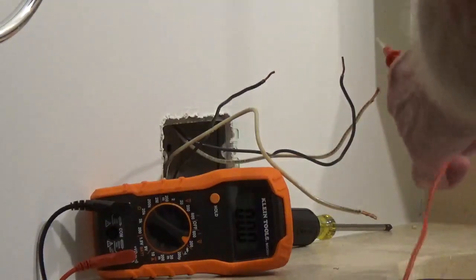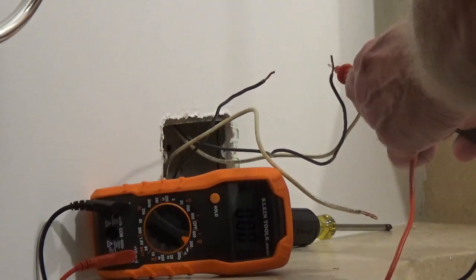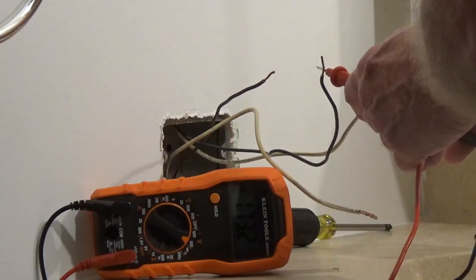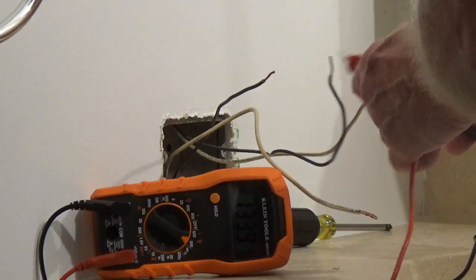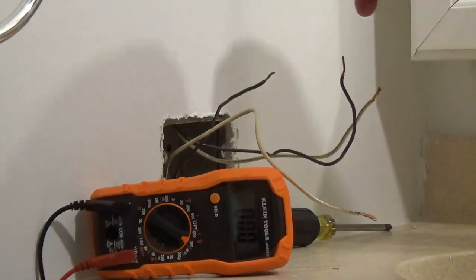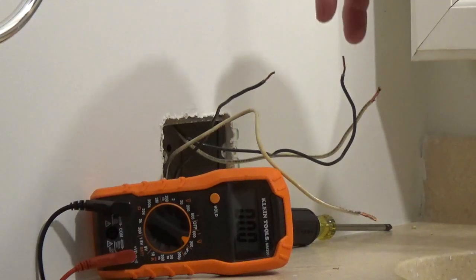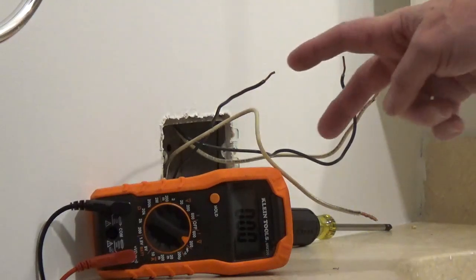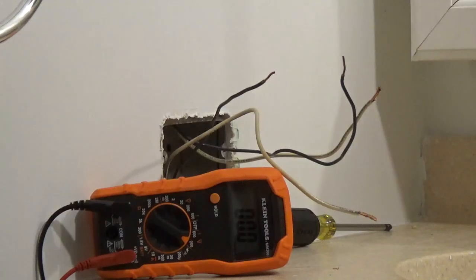So now I'm using my tester. I'm pressing it onto the hot wire and the neutral and you can see it's 120 volts. When I touch these two, there's nothing. So I know that these two wires are coming in from the service panel and now these are the two wires that I will connect to the line side of the GFCI. These two wires will be on the load side.